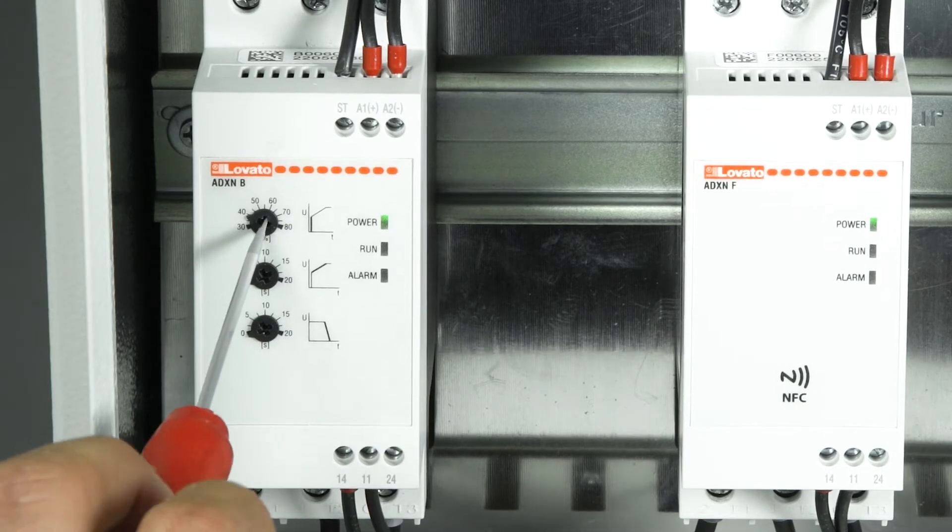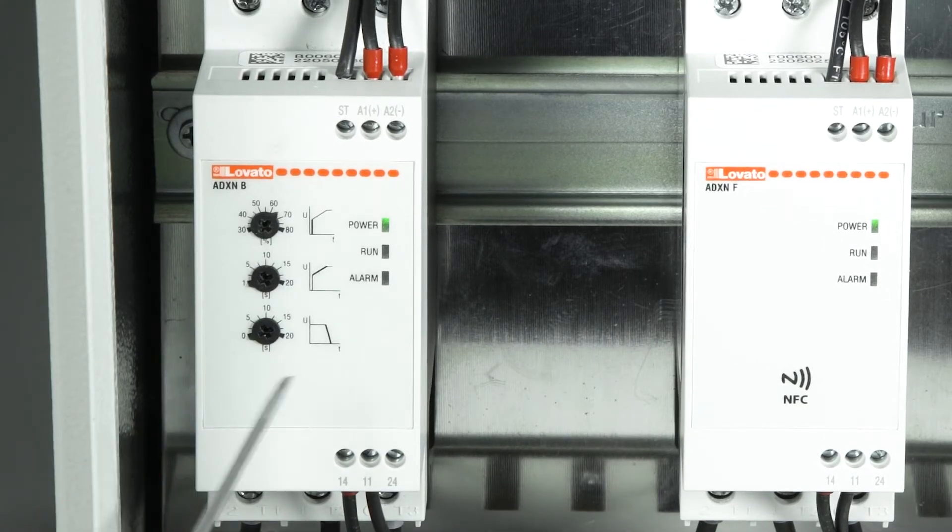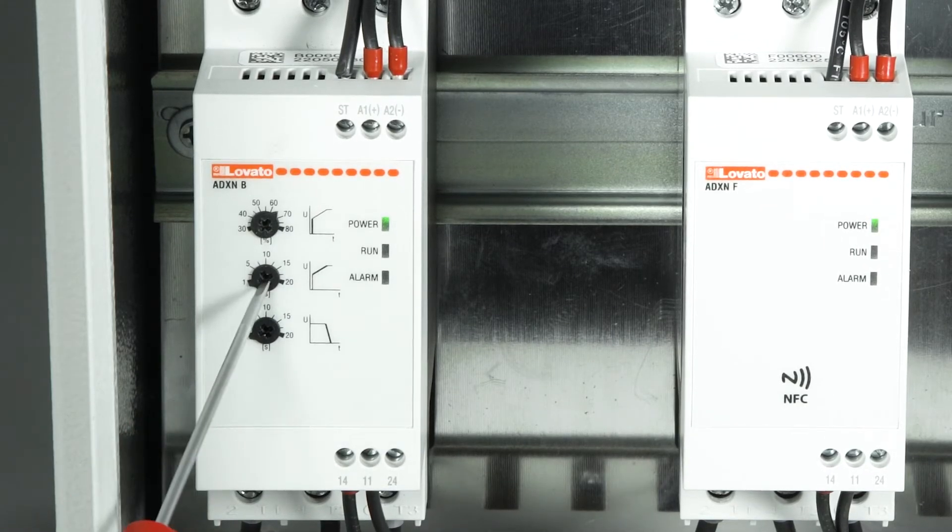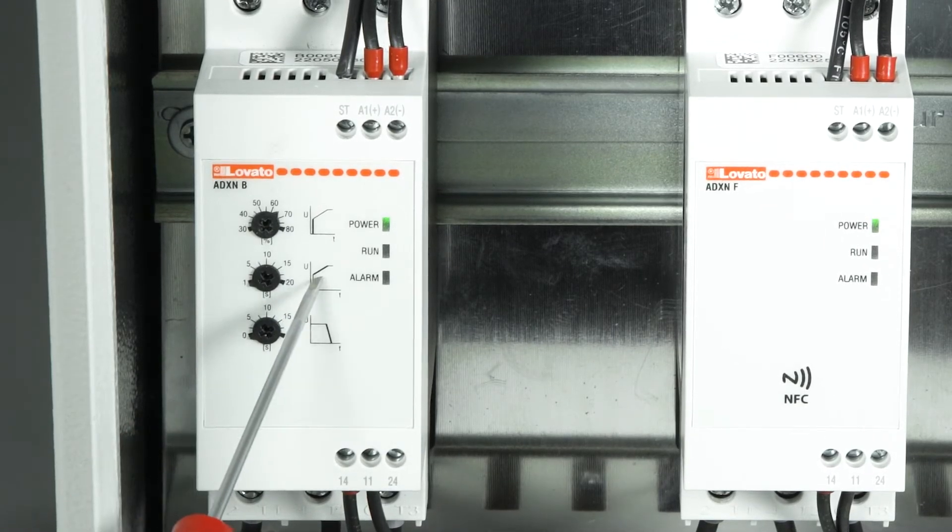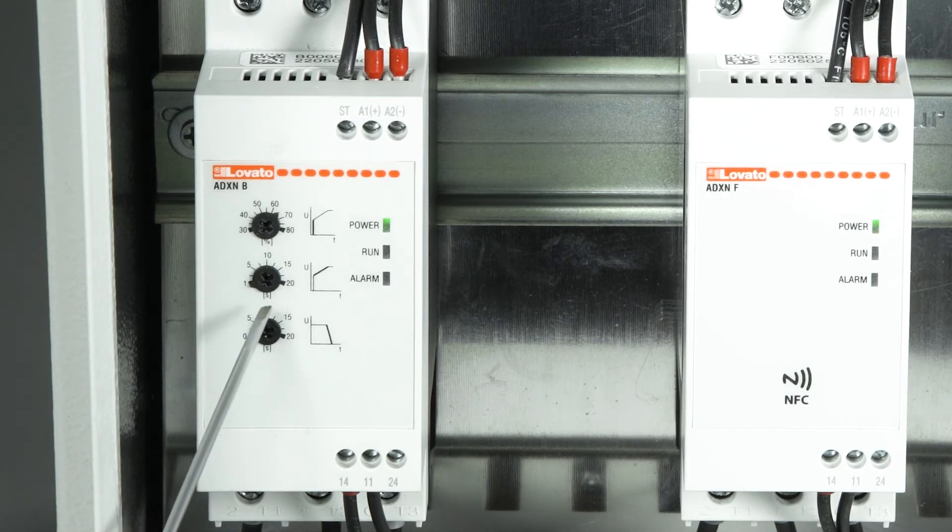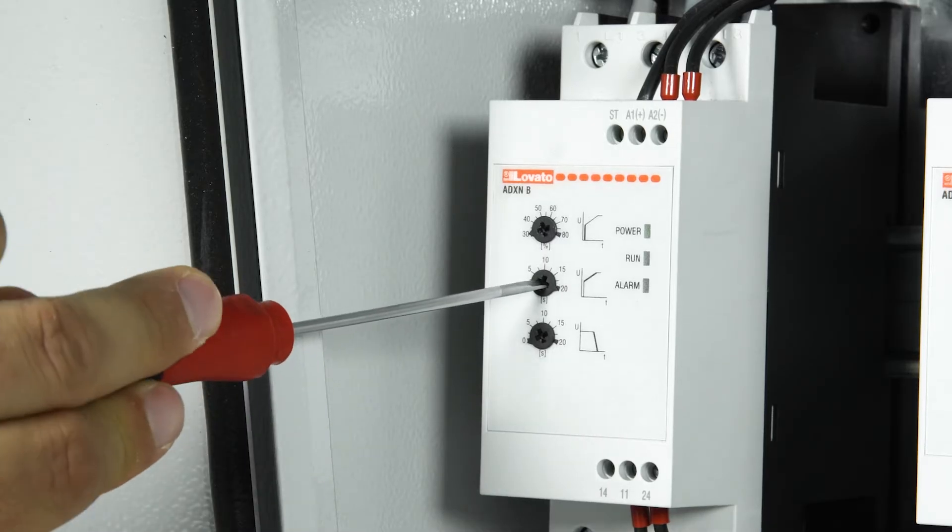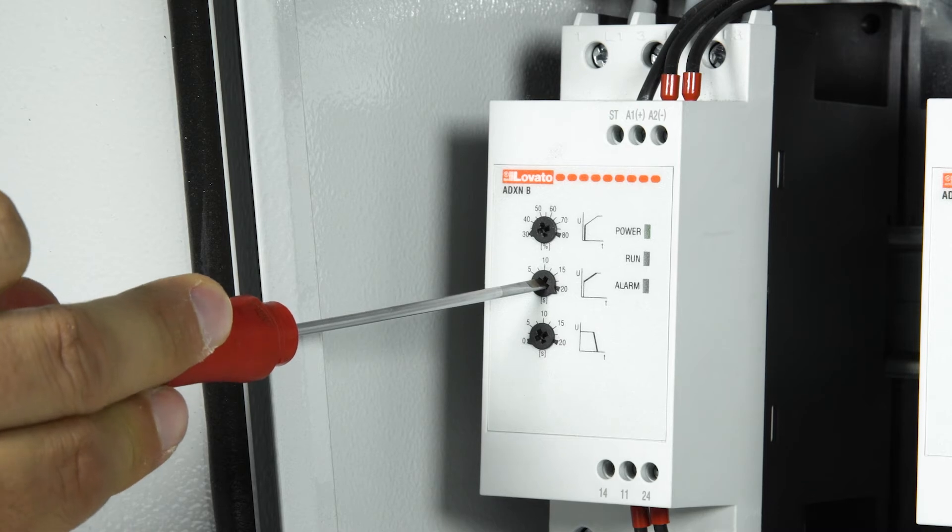The second potentiometer is used to set the acceleration ramp, which is the time taken by the soft starter to reach the full voltage. This can be adjusted from 1 to 20 seconds.